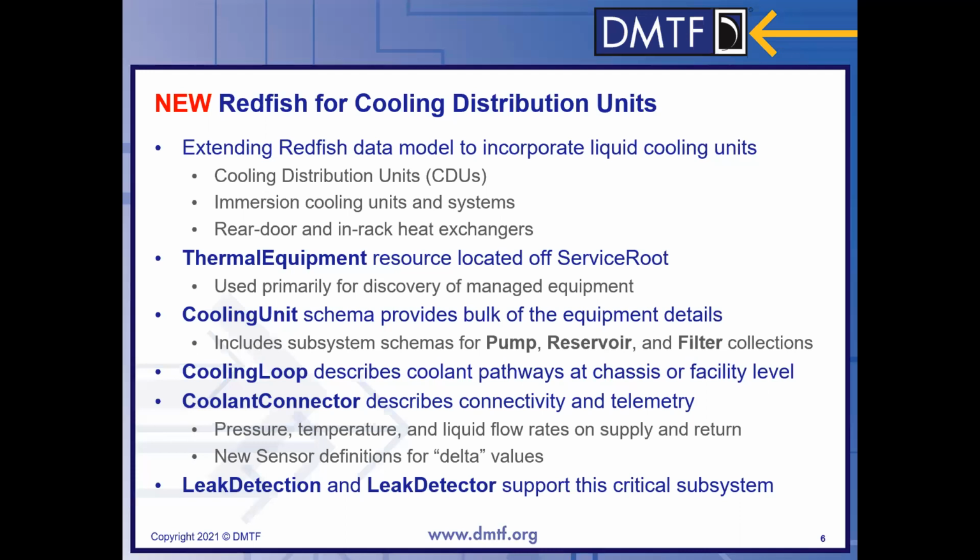But our coverage expected in this first release is we focused, in terms of mockups and the viability of the first release, on rack-based or rack-mounted cooling distribution units, or at least those types of units intended to cool a rack or a set of racks. Also immersion cooling units or immersion systems, as those are also a hot topic right now. And then also heat exchanging units, either freestanding or part of a CDU, or something like a rear door or an in-rack heat exchanger.